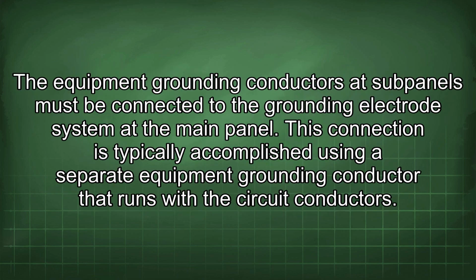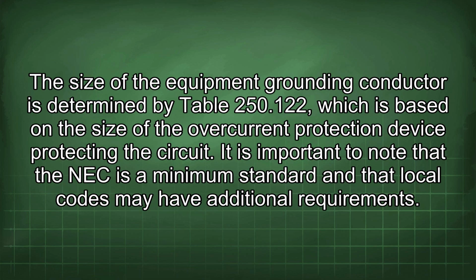The equipment grounding conductors at subpanels must be connected to the grounding electrode system at the main panel. This connection is typically accomplished using a separate equipment grounding conductor that runs with the circuit conductors. The size of the equipment grounding conductor is determined by Table 250.122, which is based on the size of the overcurrent protection device protecting the circuit.